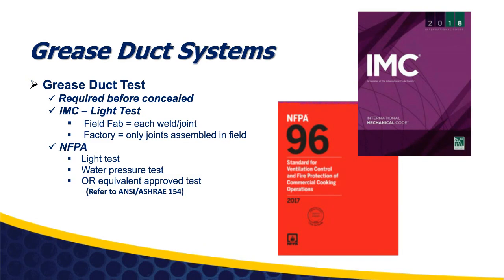All right, system inspection is going to be required, or at least hopefully is going to be required, by the local jurisdiction before the system is concealed. The International Mechanical Code is going to call for a light test. On field-fabricated product, they're saying every single weld and joint in that system needs to go through the light test to make sure it's acceptable. The International Mechanical Code is going to exclude weld joints from factory-built products and only require the mechanical joint that's assembled in the field to go through a light test.